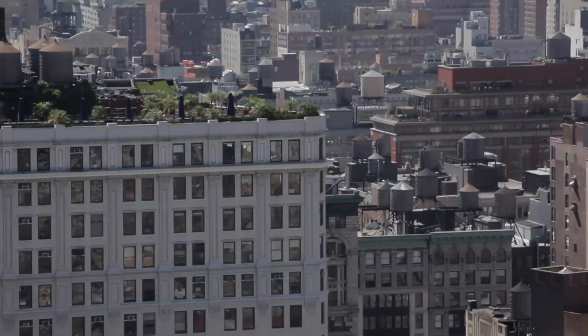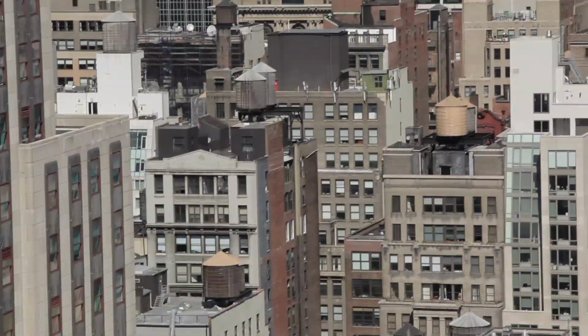Legionella levels are found in most cooling towers, but at a very low level. It's when those levels exceed a certain amount that the warning bell goes off. One of the reasons it has come back up is people trying to effectively operate their equipment are trying to bring down some of the temperatures in their cooling towers, and it's not having a chance to kill off the disease.